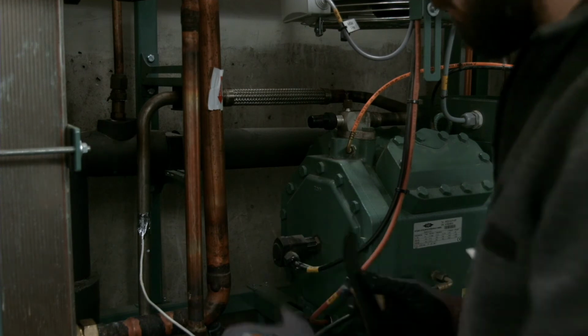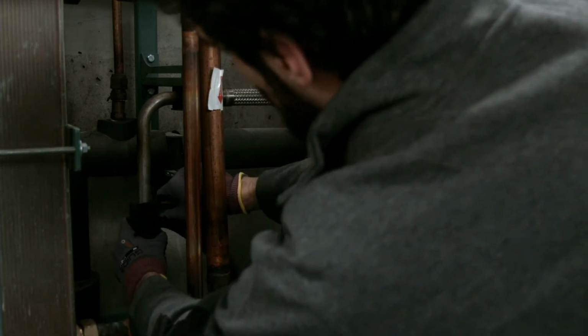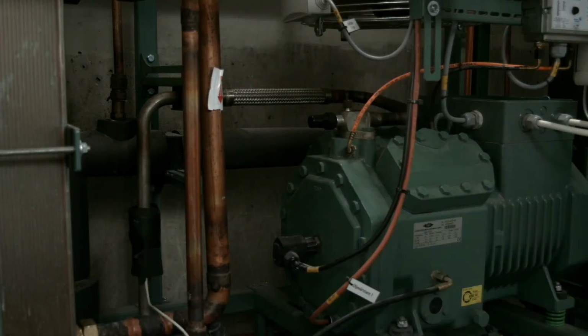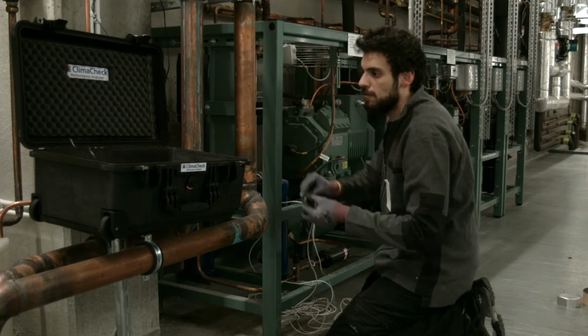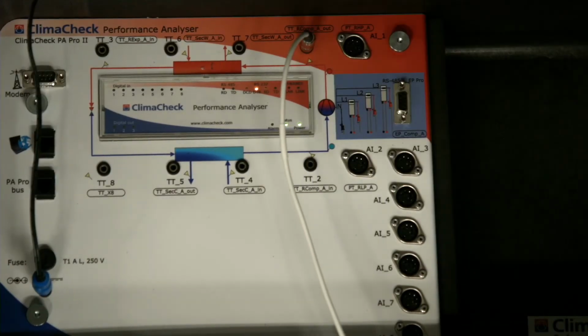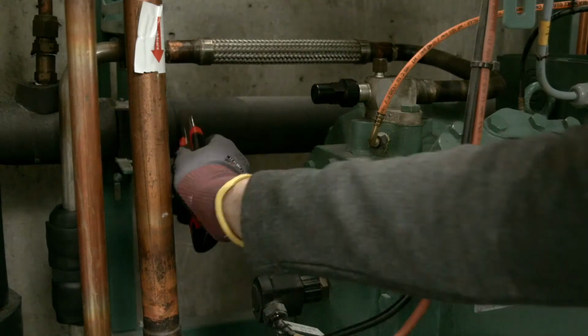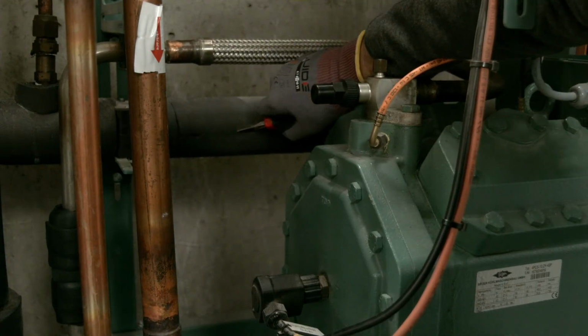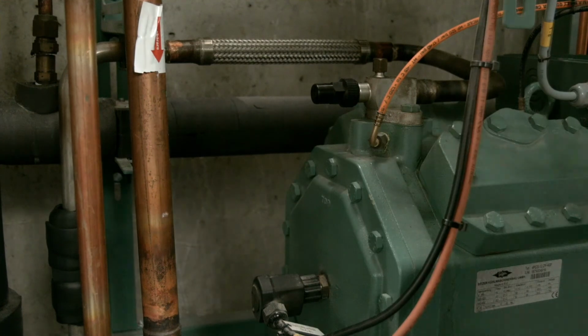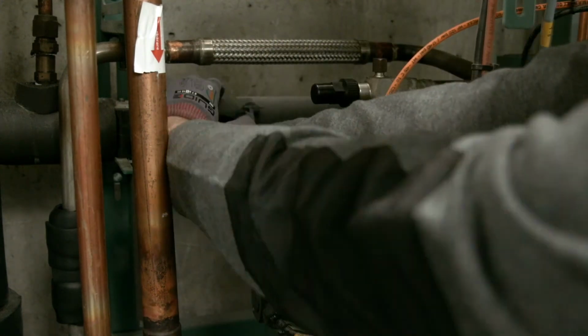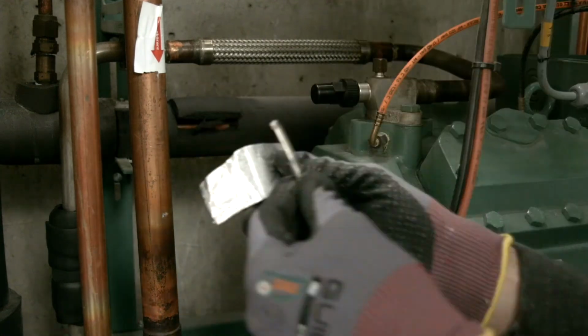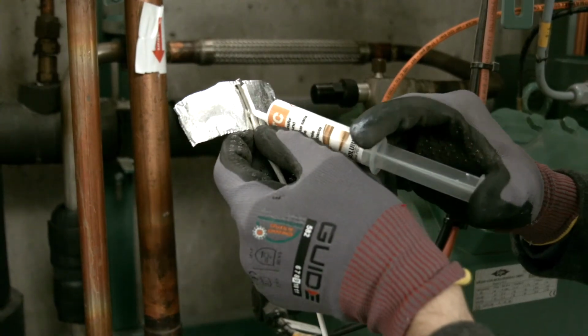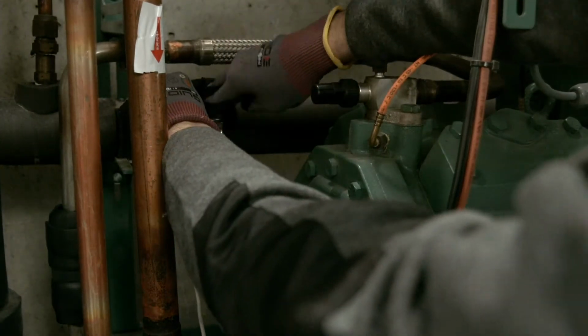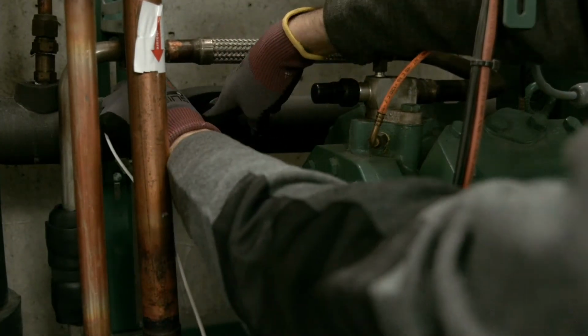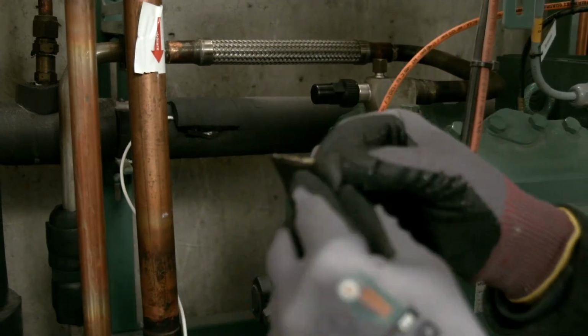Each sensor takes only a few minutes to connect. In a permanent version or installation, I should say, these cables will be run neatly through cable tray. This sensor has now been connected to the discharge of the compressor. Where a suction line is already insulated, you can neatly cut open the insulation, put the heat paste on your sensor and the silver foil, then fix the sensor in position on the line, reseal the insulation and make a really neat job of it.